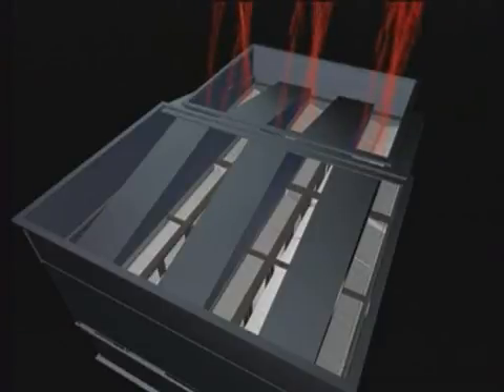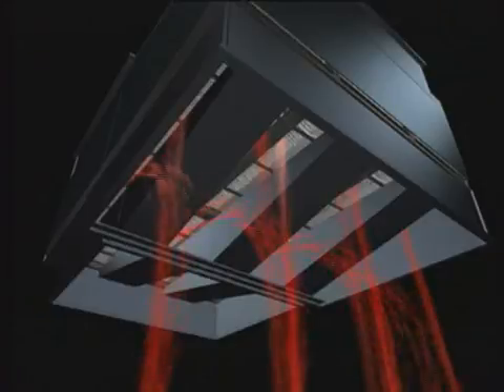In the example shown, the hot gas enters the large flanged opening and is ducted to one side of each plate. This duct runs the entire length of each plate row, or street. The gases flow down through the plates and exit on the opposite side of the plate, where they are collected by the lower distribution hood and ducted to the large flanged outlet.